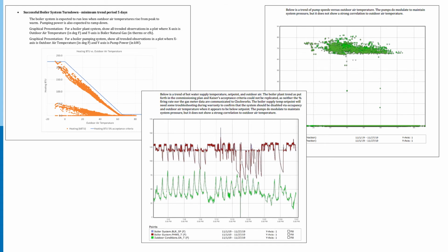They say I'm crazy. But this kind of shows you in data form that the boiler system here is pretty much running independently of the outside air temperature. There are some dips. When we get to 75 degrees, this heating system drops off by about 30%. But other than that, it just sort of runs, and it really runs almost independently of the outside air temperature. This commissioning team didn't even try to plot the boiler capacity versus the outside air temperature because there's obviously no relationship. The chart up in the top right is the pump speed.